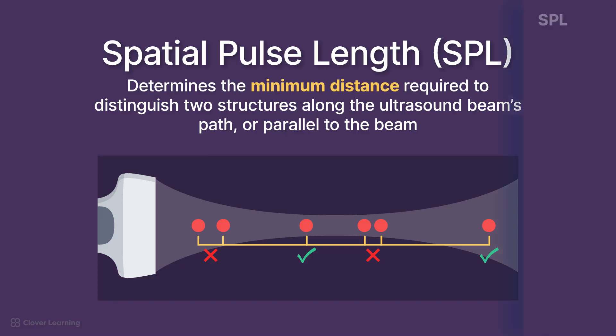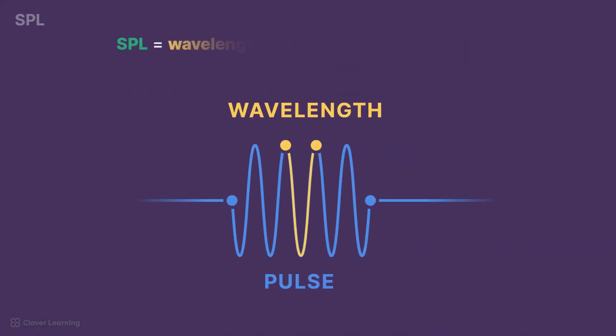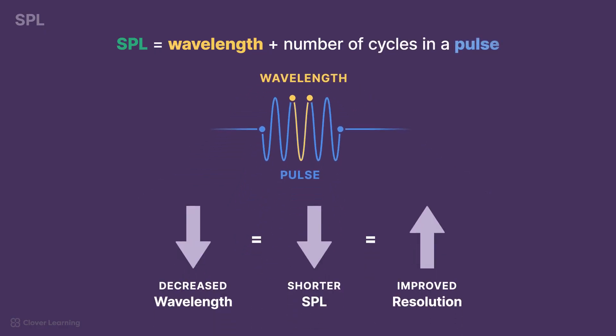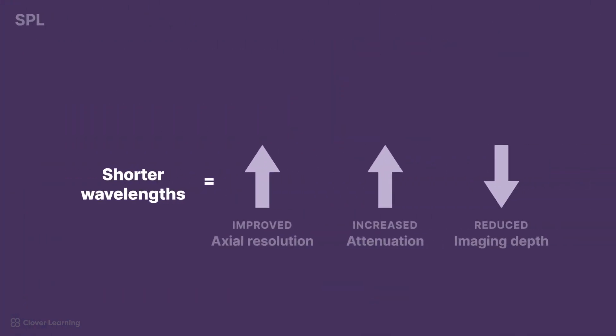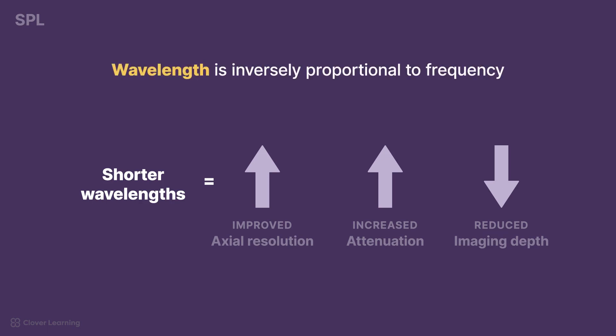SPL determines the minimum distance required to distinguish two structures along the ultrasound beam's path, or parallel to the beam. Since SPL is the product of wavelength and the number of cycles in a pulse, decreasing the wavelength shortens SPL, allowing improved detail resolution. Higher frequency transducers generate shorter wavelengths because wavelength is inversely proportional to frequency. While this improves axial resolution, it also increases attenuation, reducing penetration depth.